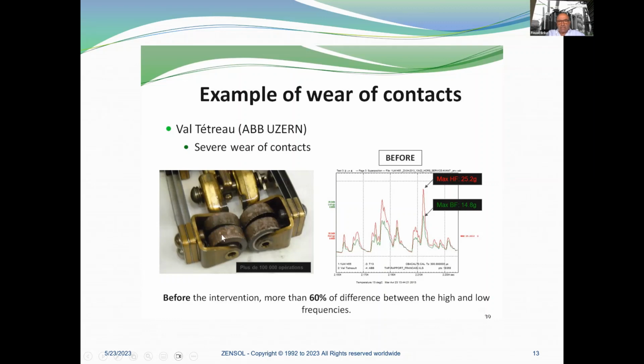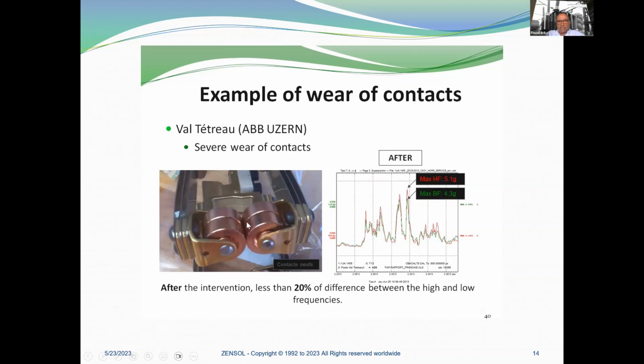Here you can see severe wear of the contacts. And here you have a superimposition of the high frequency and low frequency envelopes. Before the intervention, there was more than 60% difference between the high and low frequency. This is like an alarm that something is maybe wrong inside, and effectively, this is what you can see here. After the repair, after the intervention, there is less than 20% difference between the high and low frequencies, as you can see here.